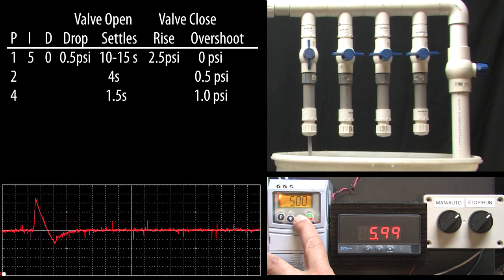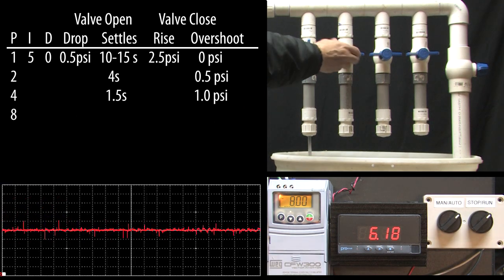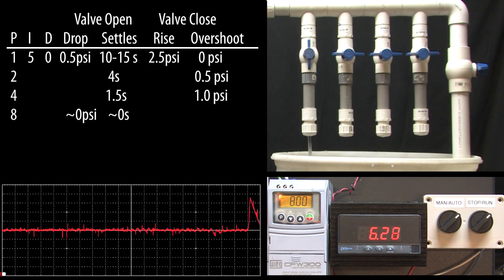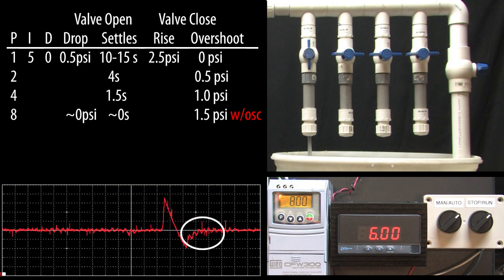We'll assume we do care so let's keep going and double P again to see what happens. I'll open the valve and wow! The system recovered so fast the pressure drop is almost non-existent. But, the abrupt valve closing is now causing a 1.5 psi overshoot and worse, we're starting to see some oscillations showing up in the recovery. When you start to see oscillations like this, you know you're pushing things too hard and it's time to back off to the previous setting.